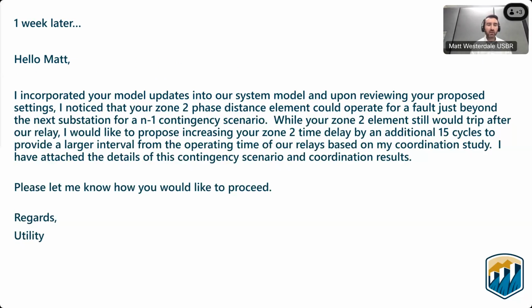But they did notice a coordination issue. For a specific N-1 contingency scenario, they felt that we needed to increase our zone 2 time delay by an additional 15 cycles, to provide a larger interval. This was a proposal from them to make an additional change, and they provided details of that contingency scenario and the results from their evaluation. So they're indicating that they had comments and issues, and they need a response from me on how I would like to proceed.